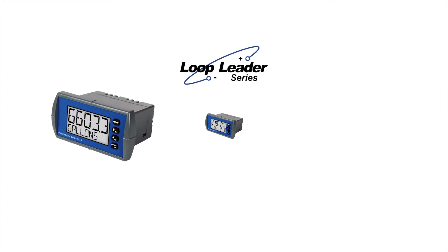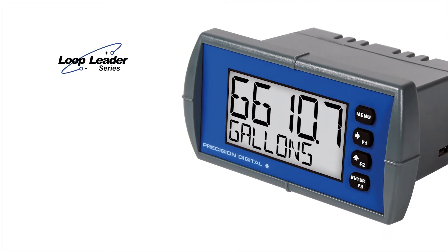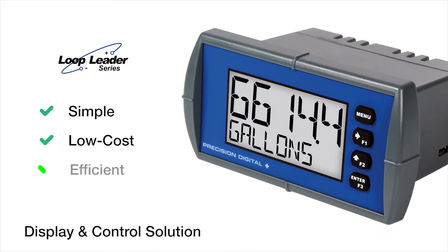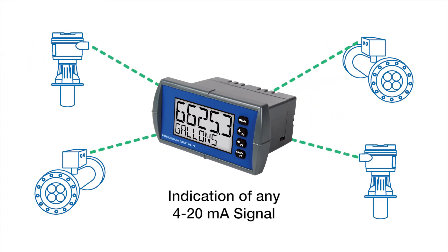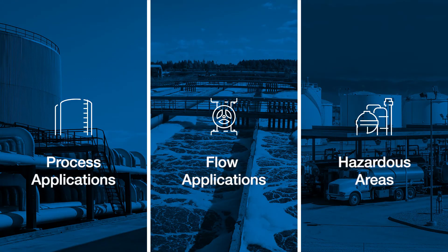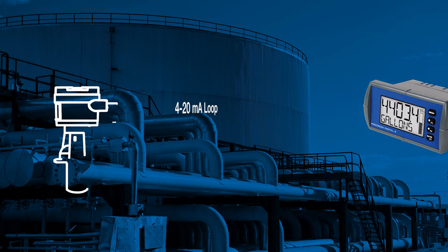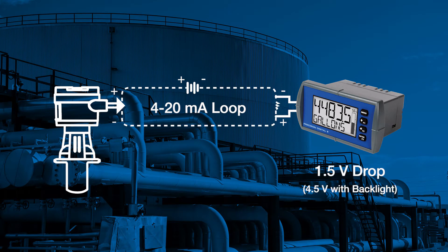The Loop Leader Series is a line of loop-powered 1/8 DIN panel meters designed to provide you with a simple, low-cost, yet highly efficient display and control solution. These meters provide convenient and informative indication of any 4 to 20 milliamp signal and can be installed virtually anywhere because they get their power from the 4 to 20 milliamp loop and only drop 1.5 volts.